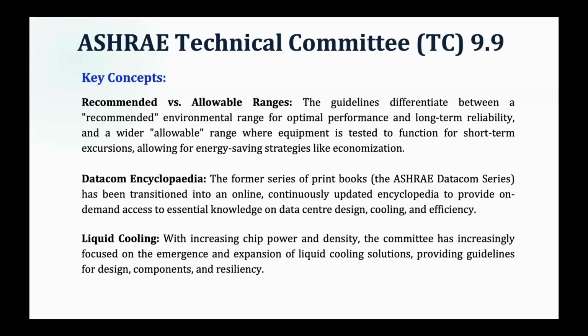Technical Committee TC 9.9 recommends what should be the maximum and what should be the allowable range within the data center, both in temperature and humidity. Because higher humidity will condense at some point and may create short circuits and electrical hazards. And very dry air sometimes will create static, and since the servers have very sensitive electronics, that may damage the equipment in some way or the other.